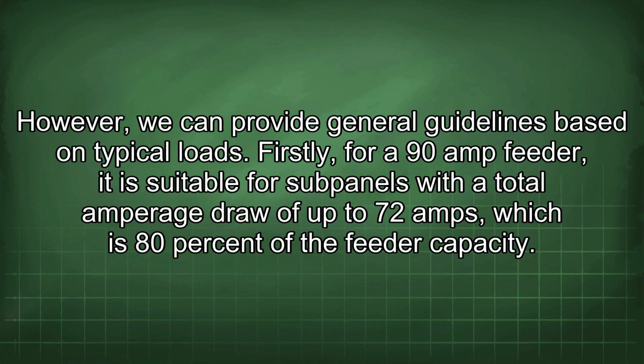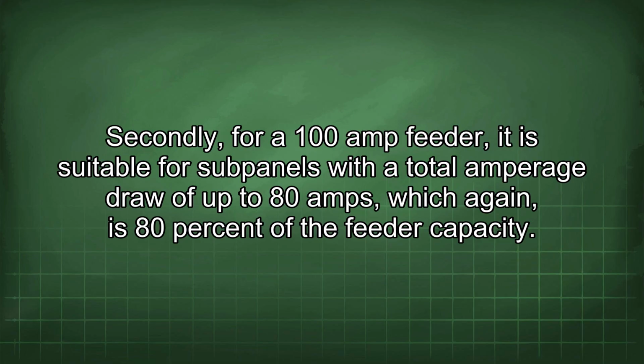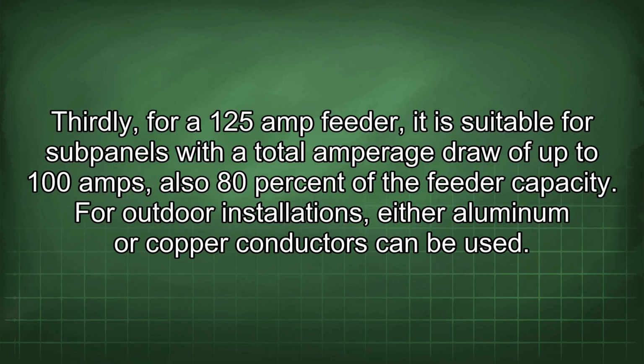Firstly, a 90 amp feeder is suitable for subpanels with a total amperage draw of up to 72 amps, which is 80% of the feeder capacity. Secondly, a 100 amp feeder is suitable for subpanels with a total amperage draw of up to 80 amps, which again is 80% of the feeder capacity. Thirdly, a 125 amp feeder is suitable for subpanels with a total amperage draw of up to 100 amps, also 80% of the feeder capacity.